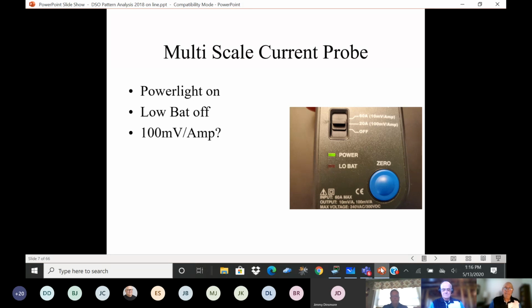What does this mean? If you look in the parentheses by the 20 amp setting, it says 100 millivolts over amp. What that really means is a current probe generates a voltage - specifically, a 100 millivolt signal for every amp that it sees.